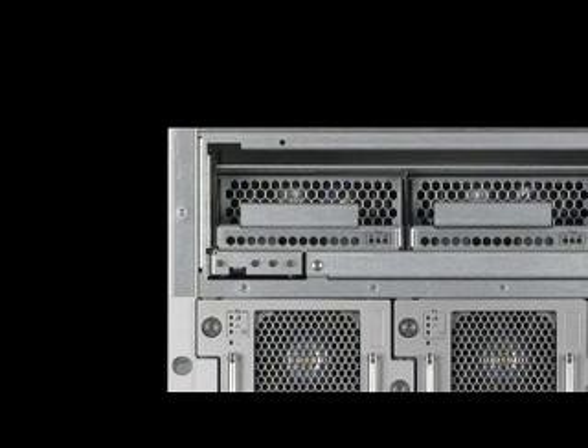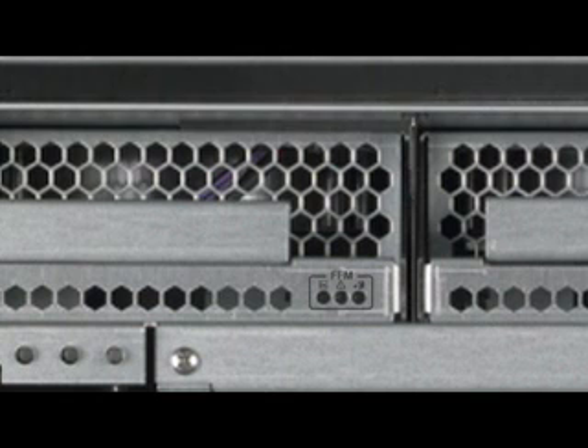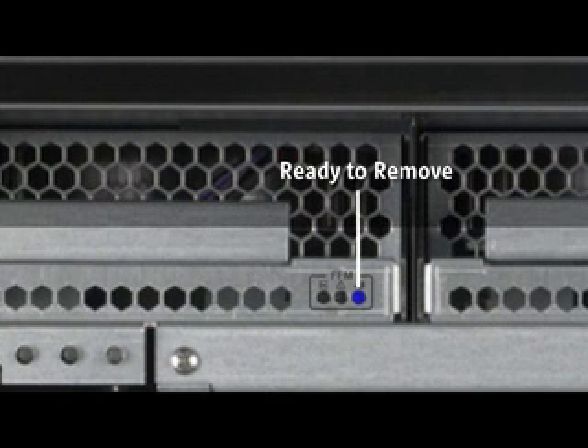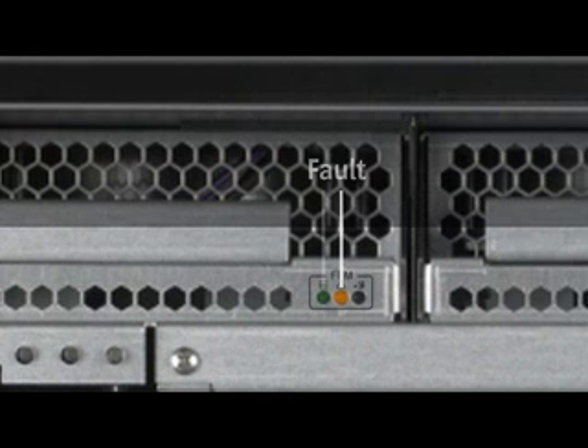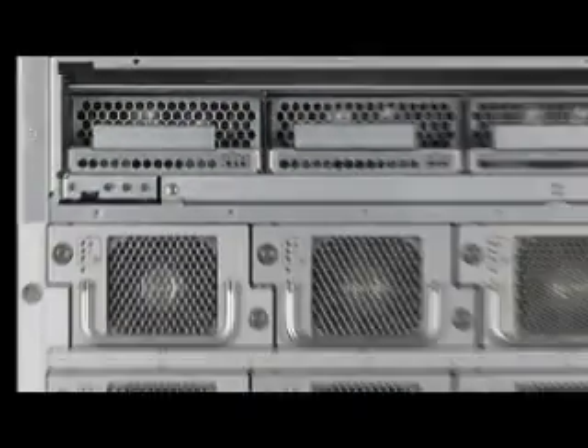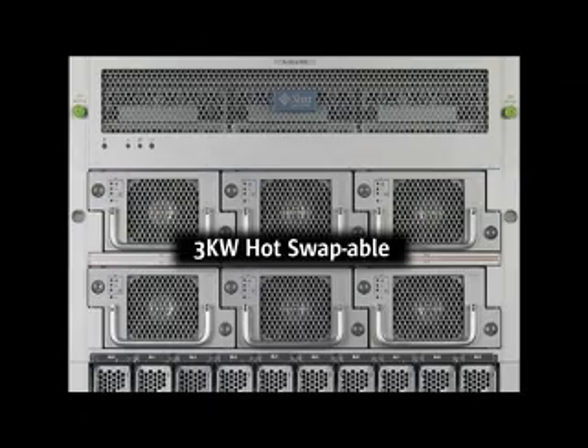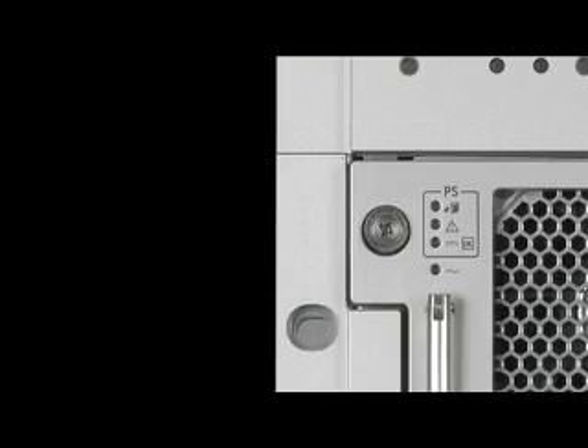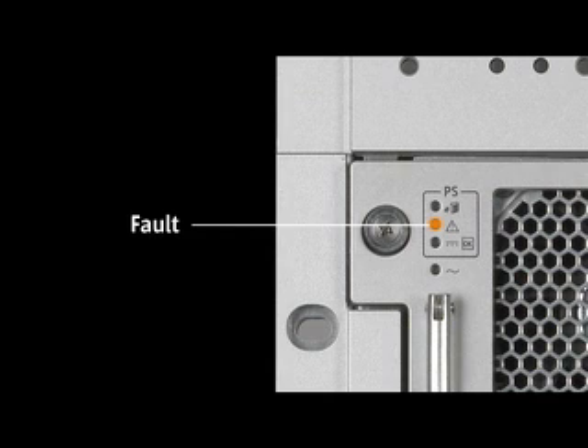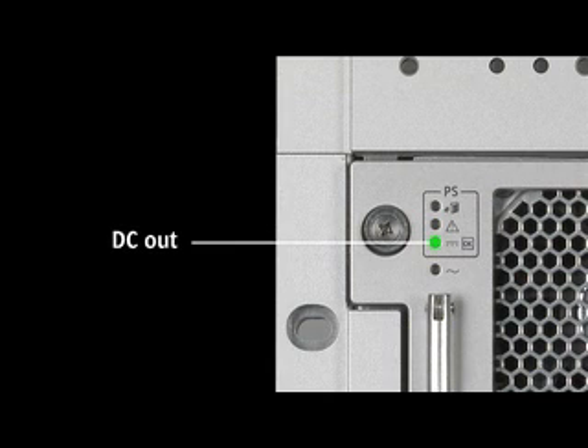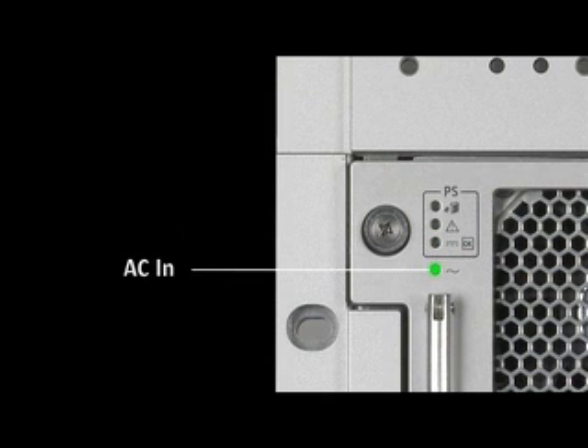These hot swappable components have 3 indicator LEDs: ready to remove, fault, operating normally. The 6 power supplies of the Sunblade 8000 modular system are all 3000 watt hot swappable. Each has 4 indicator LEDs: ready to remove, fault, DC out is lit, unit is operating normally, AC in is lit, unit is receiving power from inlet.